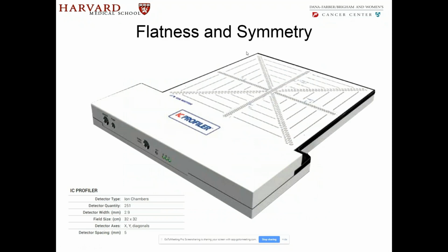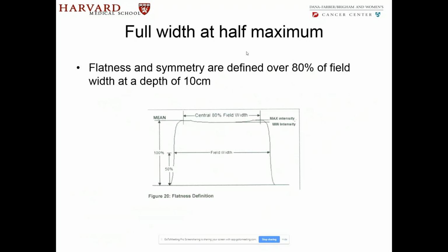The next is information about the beam. Is the beam flat and symmetric to within the requirements that the manufacturer has specified? So what do flatness and symmetry mean? Flatness is defined over 80% of the field width at a depth of 10 cm. So flatness and symmetry are always defined at a depth of 10 cm. If you look at this region as the full width, then at 80% is where we go out and calculate.